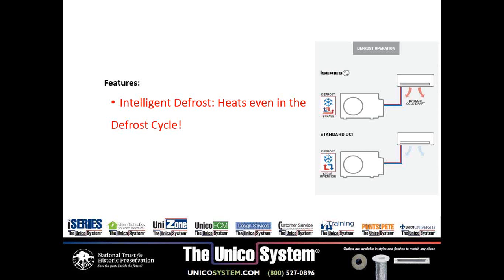And a couple of things that this does that really lends it to heating is, first of all, it has an intelligent defrost. What the intelligent defrost does is, instead of doing the standard defrost where you shut down from heating and go into cooling to defrost the outside coil, Unico has a hot gas bypass. There's a hot gas bypass coming directly off of the compressor, which then melts the outside ice. Now, what makes this different is you can have heating with the heat pump even when it is in defrost mode.